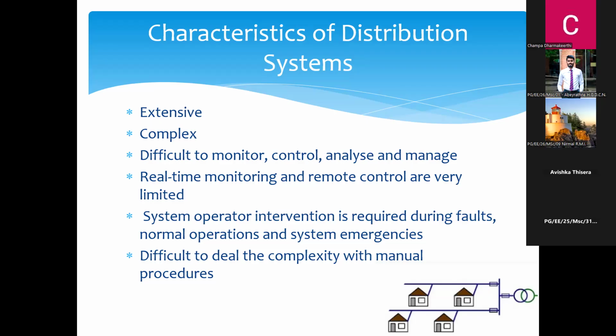Again, real-time monitoring and remote control are very limited in these distribution networks. It is limited to big customers, bulk consuming customers, and load break switches and air break switches. Up to that level only, remote controls are available. Beyond that, even in distribution transformers, we don't have the ability to control. System operator intervention is required during faults and normal operation as well as during system emergencies. We need to have a system operator. No automated arrangements are there. It is difficult to deal with the complexity with manual procedures.